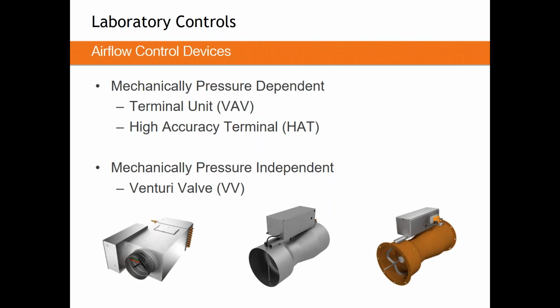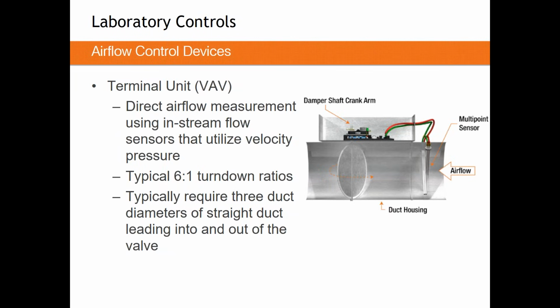Across a line in the sand is the Venturi valve. Mechanically speaking, it's completely independent of pressure. Airflow and pressure in that device are in no way, shape, or form linked together. So let's start here with the most simple of the three devices. You've all seen a million of these and applied a million of these things. It's an extremely simple device, the VAV box. A VAV box is just a damper with a method of measuring airflow.